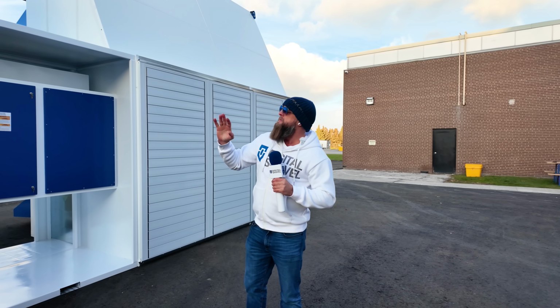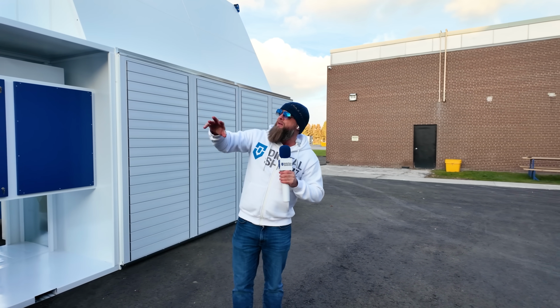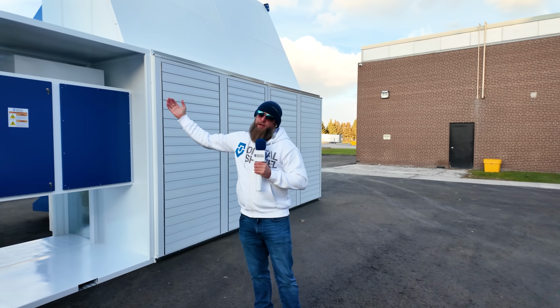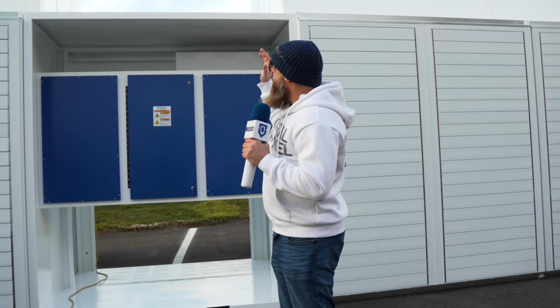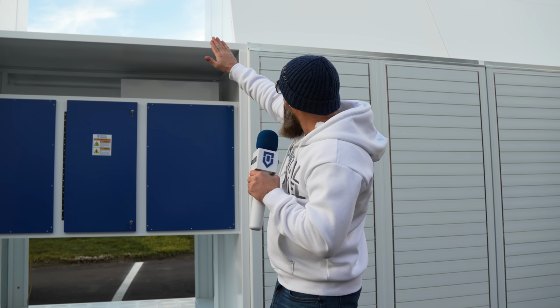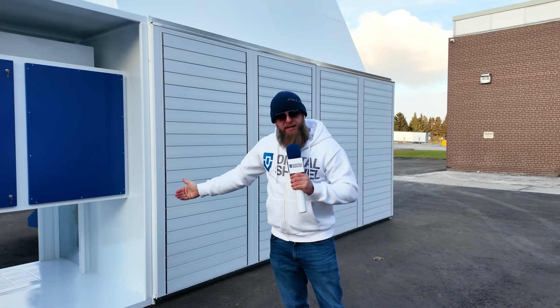One of the other major benefits of our 2-story unit is it prevents backflow. So the hot air that would come out from here can't easily go back over and get sucked into the intake. Since we're taking these and putting them on a truck tomorrow, we don't have it installed, but normally you would have an additional 2 panels that would connect that top section to prevent the hot air from going through, as well as 1 panel here underneath the switchgear which prevents hot air from flowing back into the intake side of the pod, which is a substantial issue with almost every container manufacturer that operates with a single story unit.